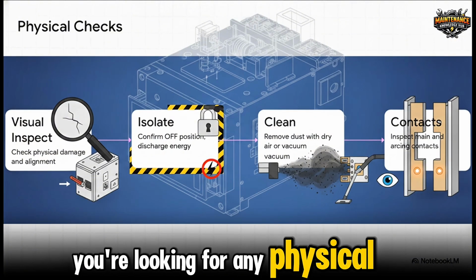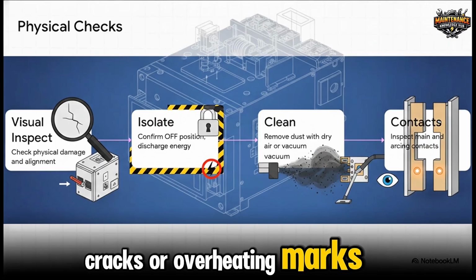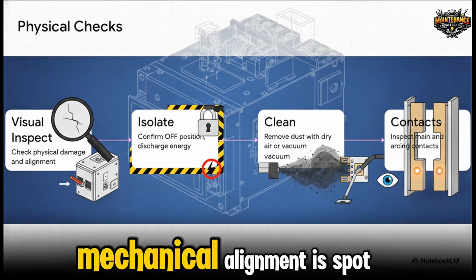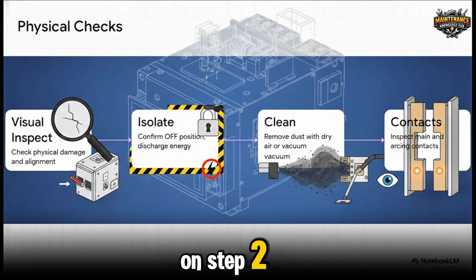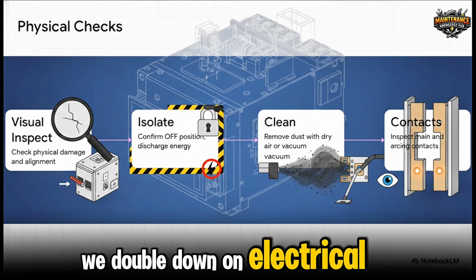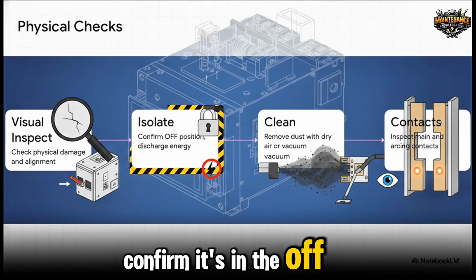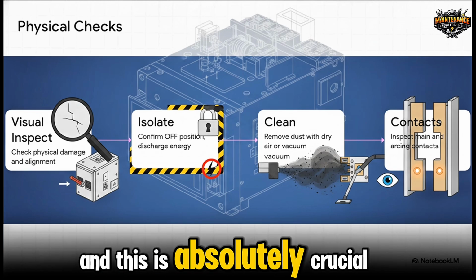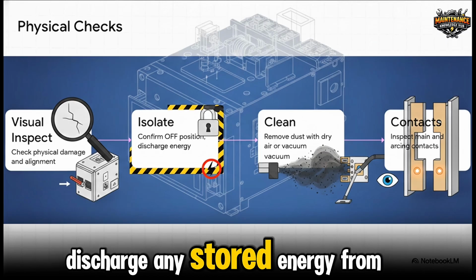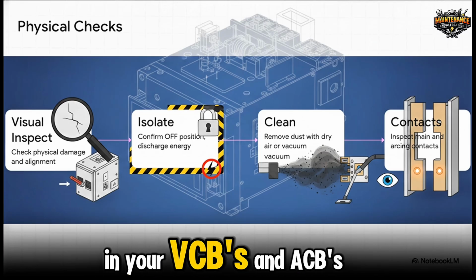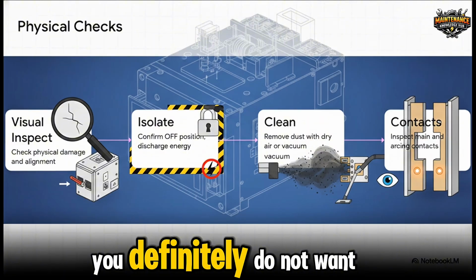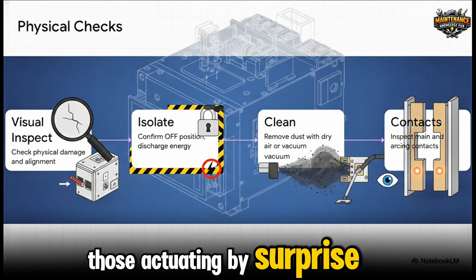You're looking for any physical damage, cracks, or overheating marks, and just making sure the mechanical alignment is spot on. Step 2, we double down on electrical isolation. Confirm it's in the off position, and this is absolutely crucial. Discharge any stored energy from the spring mechanisms in your VCBs and ACBs. You definitely do not want those actuating by surprise.